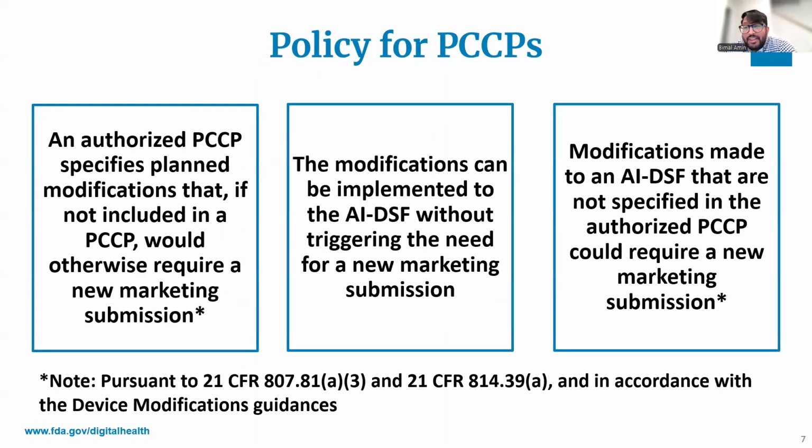So to recap, an authorized PCCP specifies planned modifications that, if not included in a PCCP, would otherwise require a new pre-market submission. The modifications can be implemented without triggering the need for a new pre-market submission once authorized. And modifications that are not specified in the authorized PCCP could require new pre-market submission.